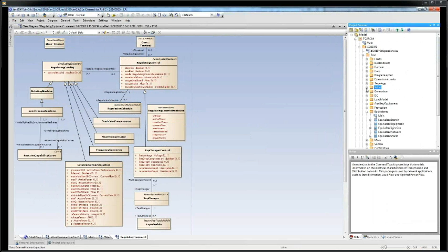The different running arrangements are the point of representing a condition where, say, line 1 connected to the following switches is out of service and switched open by these switches. That can be arranged for PowerFlow purposes or even as outputs to another simulation program, represented with the actual device statuses for different time points. There are also regulations and schedules that can be employed to set switches open or closed. Jay, does that kind of handle it?